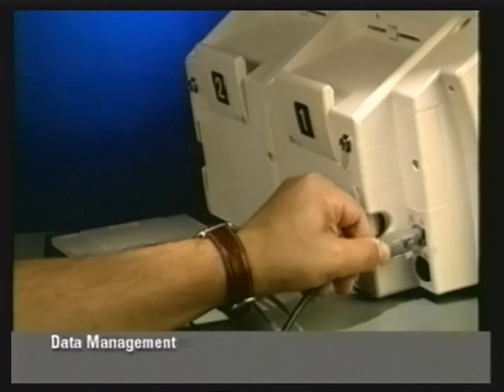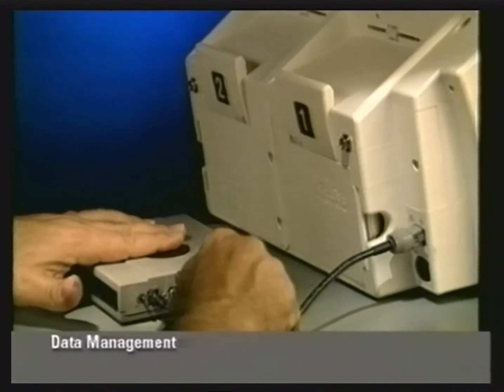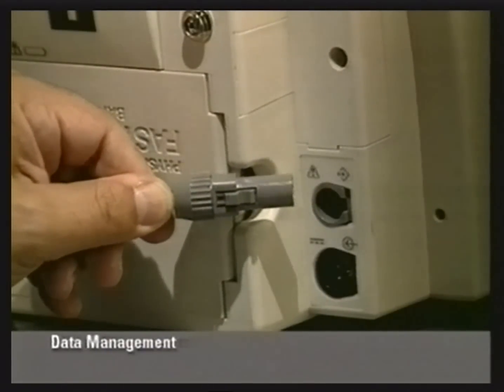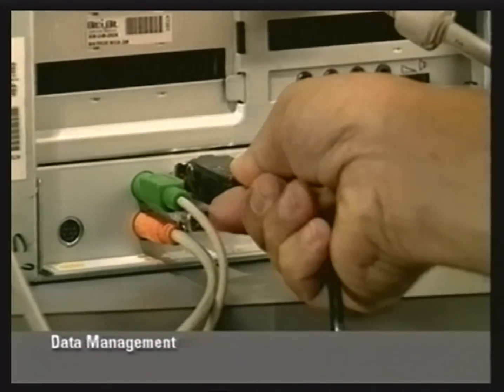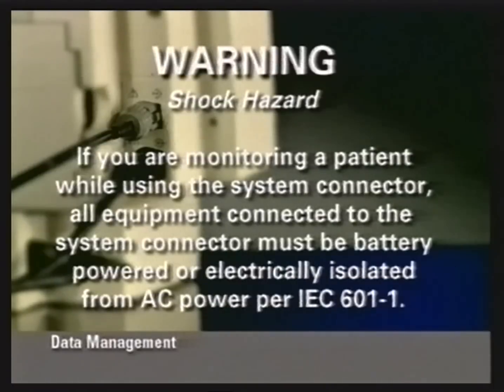To transmit patient data using an external modem, connect the modem cable to the system connector on the defibrillator and to the modem. To download patient data directly to a PC, connect the PC serial port cable to the system connector on the defibrillator and to the PC. If you are monitoring a patient and use a system connector, all equipment connected to the system connector must be battery-powered or electrically isolated from AC power. If in doubt, disconnect the patient from the monitor before using the system connector. For more information, contact Physio-Control Technical Support.